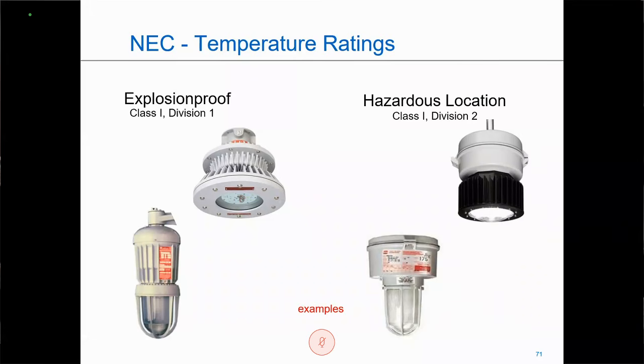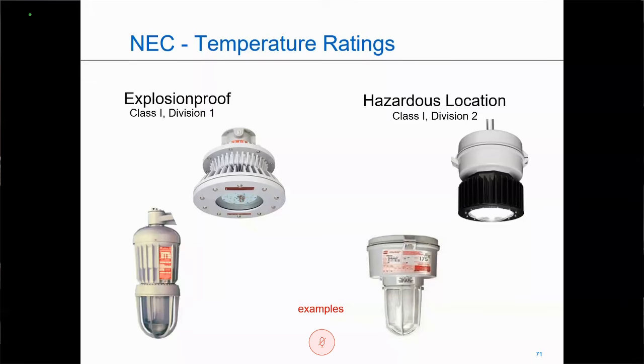Now, I think I remember a question also when we were discussing temperature ratings, when I had asked to hold it to this point of the presentation, talking about the 80% rule. What the 80% rule is that if I have a unit that its heat exceeds 80% of the auto ignition temperature of a particular gas, then I need to do one of two things. I need to use my Class 1 Division 1 lighting fixture, or I need to use a unit that is clearly marked to operate with those particular temperatures. And so that's where that 80% rule comes into play.